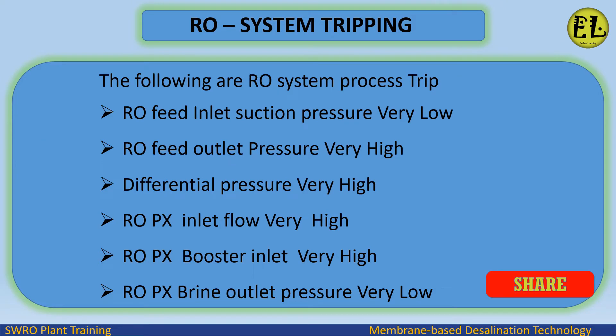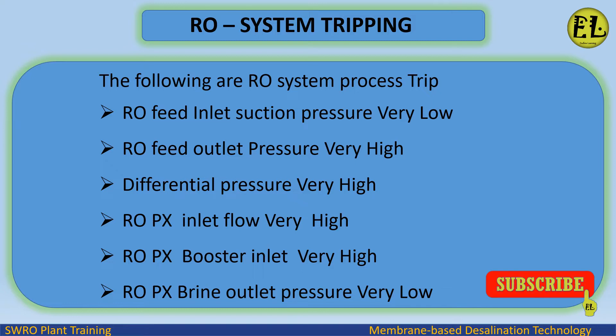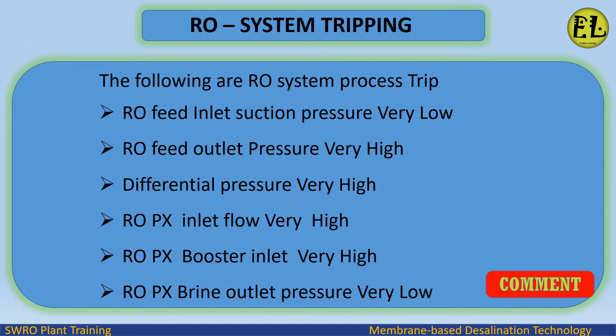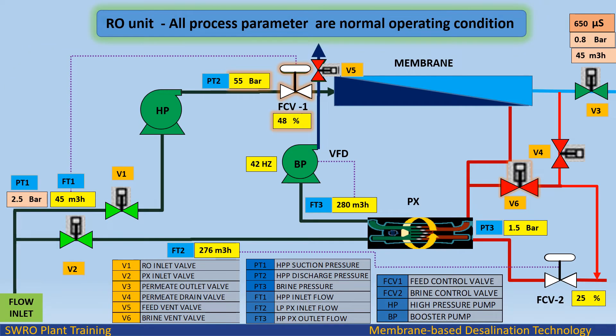The following are RO system process TRIPs: RO feed inlet suction pressure very low, RO feed outlet pressure very high, differential pressure very high, ROPX inlet flow very high, ROPX booster inlet very high, ROPX brine outlet pressure very low. RO unit all process parameters are in normal operating condition.